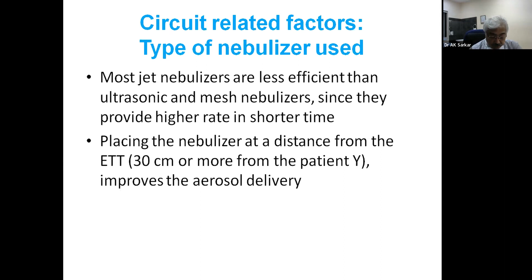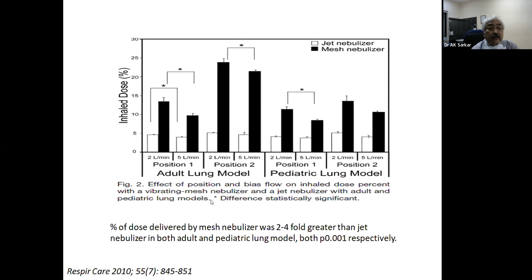So, regarding placing the nebulizer at a distance from the ET tube, a jet nebulizer should always be placed well beyond your Y connector. I'll show that and why this is important. One study has shown that a jet nebulizer has much less deposition than mesh nebulization. And when you are using 2 liters per minute of bias flow, drug deposition is higher than with high bias flow. That applies to both the pediatric lung model and the adult lung model. That is one of the things we don't often see during our ventilation.